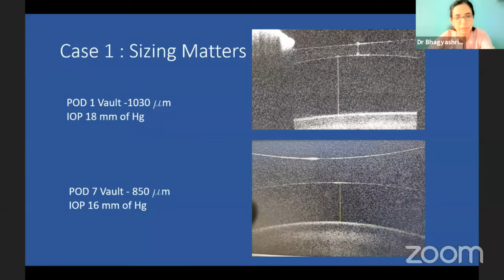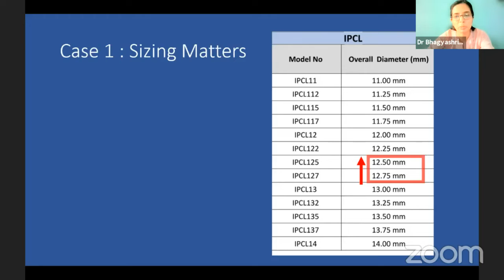For the second eye, we reordered one size smaller lens. As we know, IPCL comes in 13 sizes in steps of 0.25 mm from 11 to 14 mm, and usually one size lower lens decreases the vault by 100 to 150 microns. So we implanted 12.5 mm in the left eye, and we hit the sweet spot of 725. And the patient is doing great post-operatively.